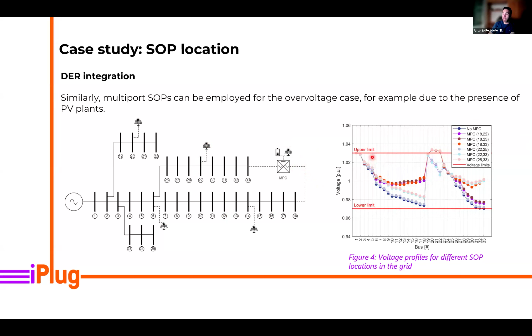In figure 5, you can see the different positions of the multiport converter. And if we take, for example, the best position up to now, that is between 18 and 33, we can see how the losses, the optimized losses thanks to the optimized operation of the soft open point, are reduced to 1/3 of the original losses in the benchmark system. In this figure, we can see also something interesting, that is in position 18-22, for example. If we optimize the soft open point in such a way that the voltages are minimized, then we increase the losses more than the benchmark case.